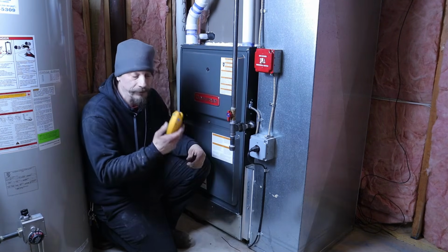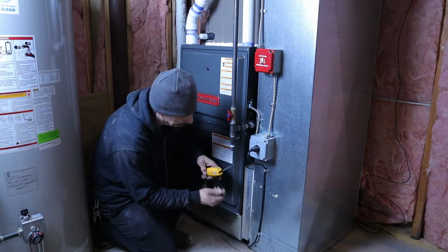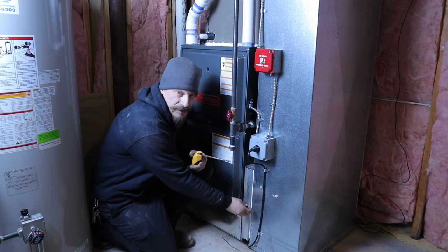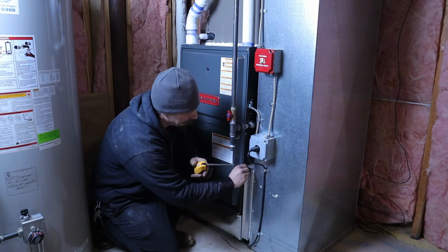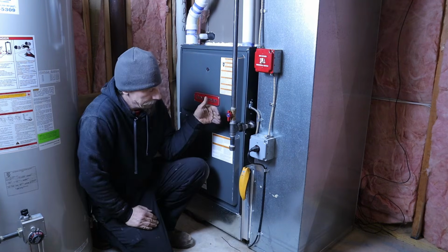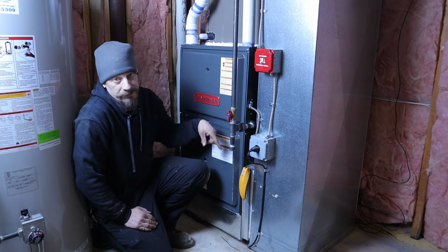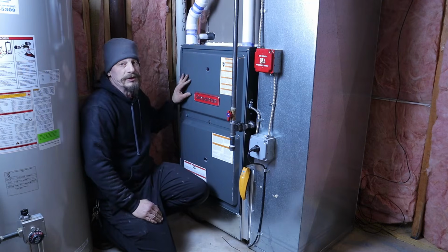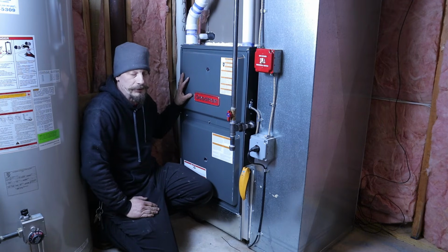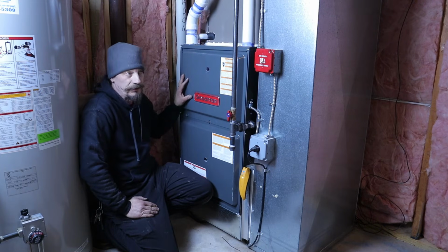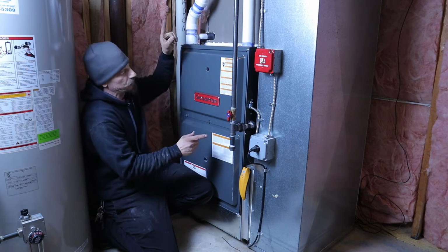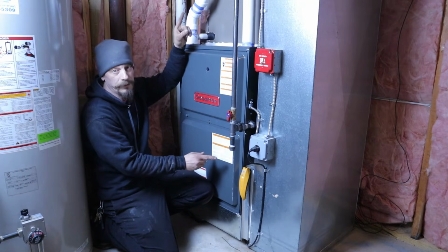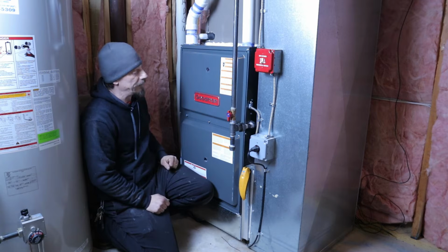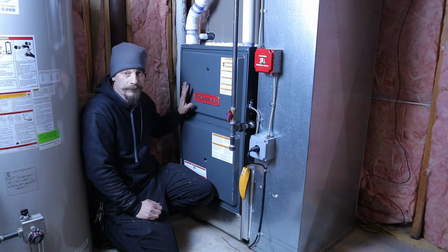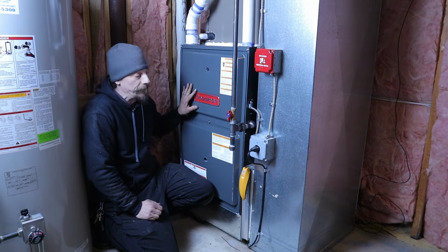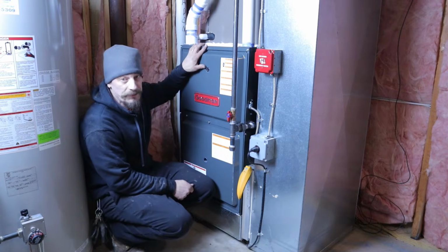I'm going to take my other probe here, and I'm going to get a temperature reading down here by the return. And this is the air coming back in from the house to the furnace to get heated up. So what I'm going to do is take the temperature difference between these two temperatures, and inside the furnace there is a sticker telling me what that temperature differential should be. So for this particular unit, it's between 35 and 65 degrees. So that's what I'm looking for. I'm looking for a temperature difference between these two probes to be within that 35 to 65 range. And that will tell me that this unit is getting proper airflow, and it's getting off on the right foot right from day one. So our Nest thermostat's powered up.